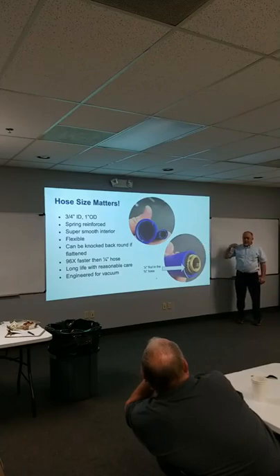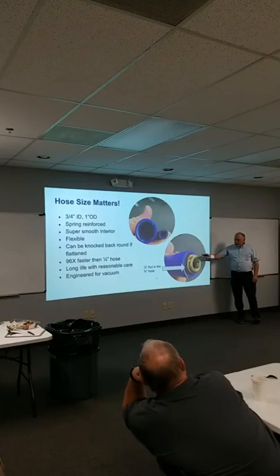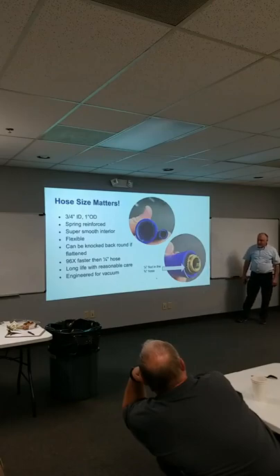We actually tested, I tested, probably about 15 different hoses before we found this hose that had the properties that we needed. And the biggest thing was it didn't outgas. We tried a lot of hoses. Ideal Vacuum makes hoses. A lot of companies make hoses. We tried a lot of them and they just didn't work well because they didn't achieve a low vacuum. This stuff had a super smooth interior. It was really flexible. It could be knocked around, flattened out. But it ended up being 96 times faster than 1/4 inch hose.